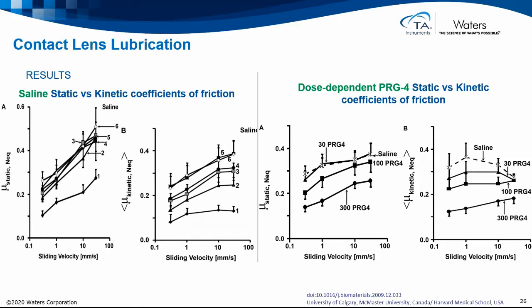So on the left, we see material in saline. And then on the right, we look at this dose dependency of this proteoglycan 4. So we see that the sliding velocities on the x-axis, and then static friction and kinetic friction are what we're seeing here. As you remember from physics class, static friction is the resistance of motion from 0. So as you start to move, you get an increase in that shear force or torque that we're measuring in the instrument. But then as it continues to slide, then that kinetic friction starts to come into play and creates less force. So let me walk you a little bit from left to right.